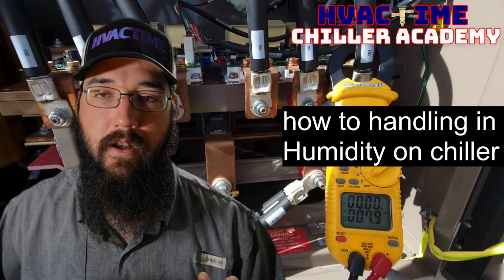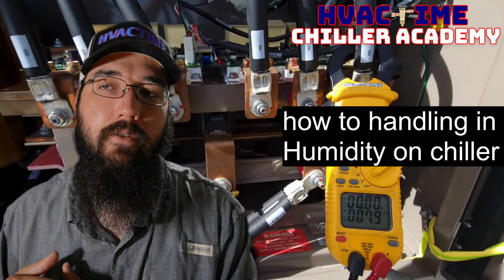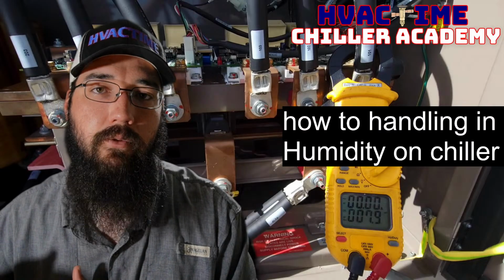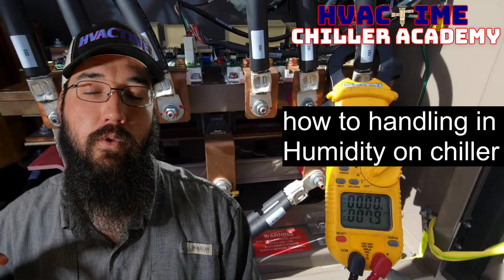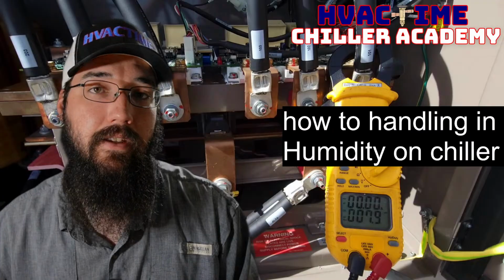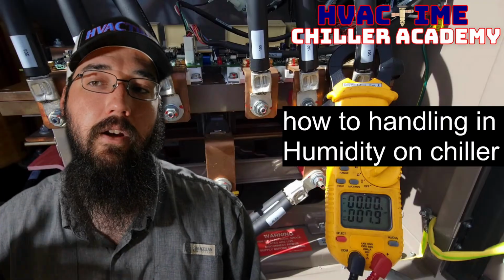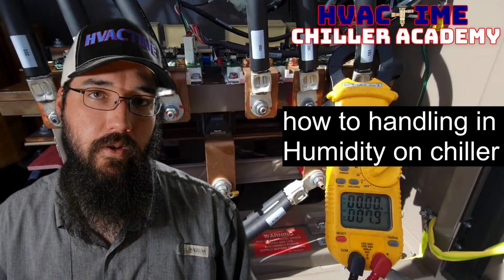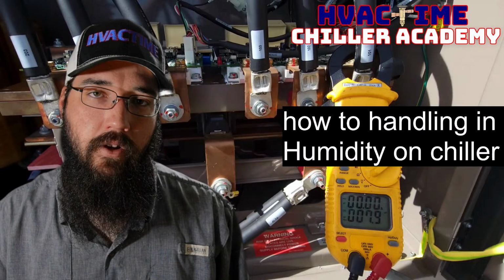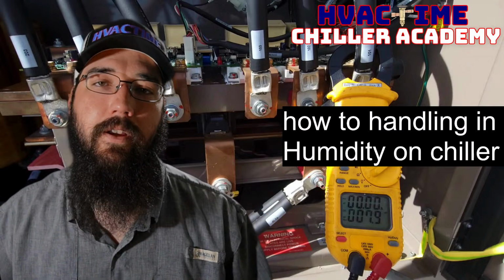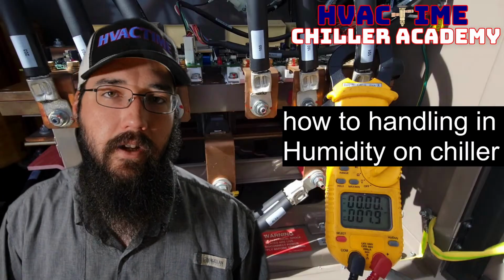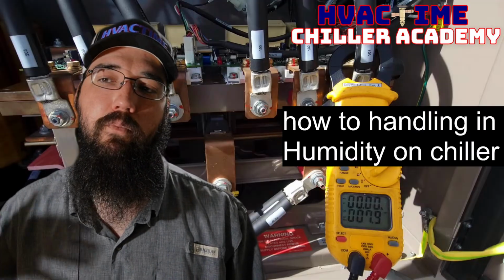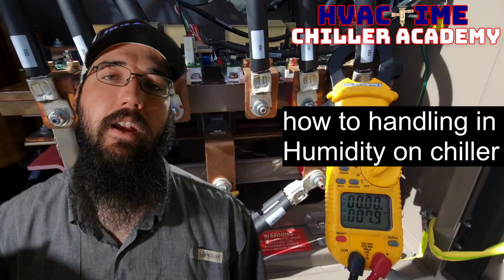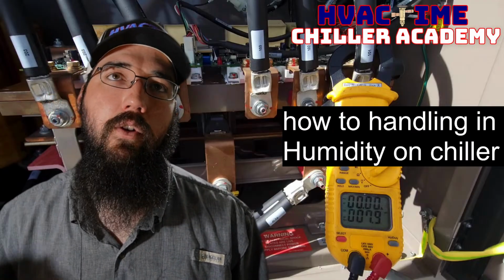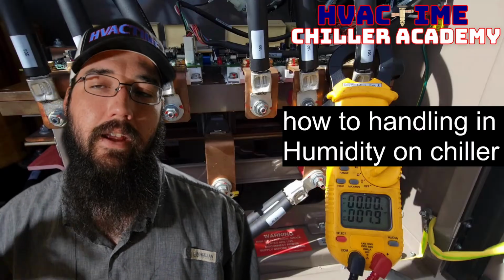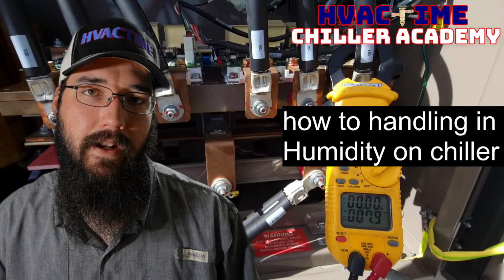Again, this is the exact same concept and theory as an RTU. If we are struggling with over dehumidification, we're pulling too much humidity out, you can speed your fan up, and at that point you'll start processing more sensible heat, less latent heat, but again, your saturation temperature will typically increase in conjunction with the CFM increasing across the coil. The water temperature is not going to track the same way a DX coil would, if you're tracking with the analogy here. So that just means that we manually raise that set point at the chiller itself. And by doing so, by getting a little bit of a warmer coil, we're not going to take in as much humidity, as much latent heat, and you'll be able to maintain a better humidity in the space.